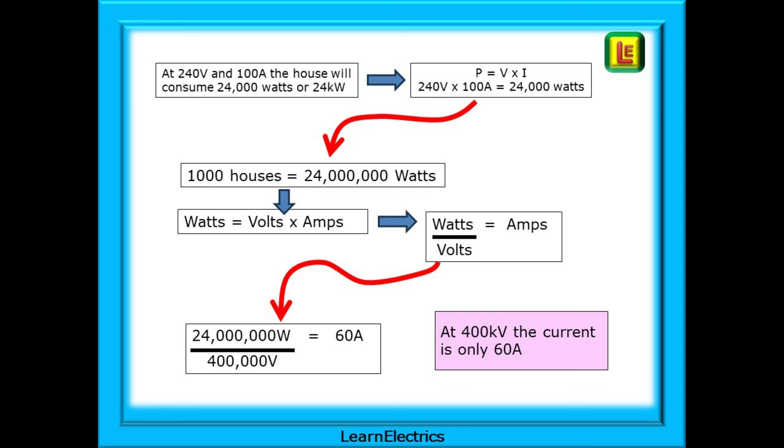Now 24 million watts divided by 400,000 volts is just 60 amps of current. This means that supplying 1,000 houses with 100 amps will only require 60 amps of current in the 400,000 volt transmission lines. A lot less current, much smaller cable sizes, less voltage drop and less heat, and a lot less weight for the pylons to support. Win-win all round.